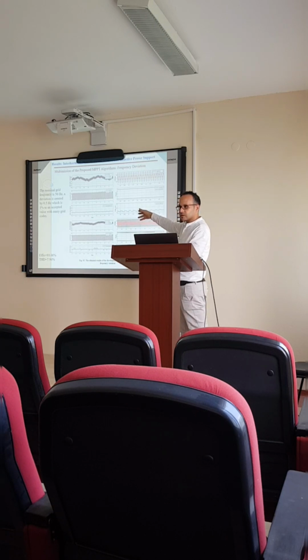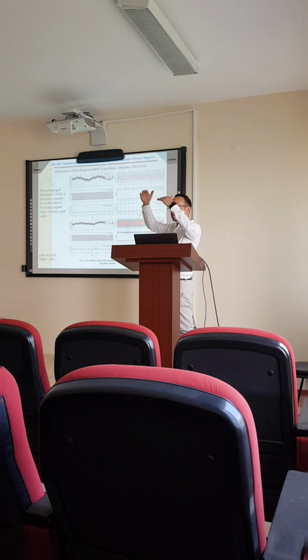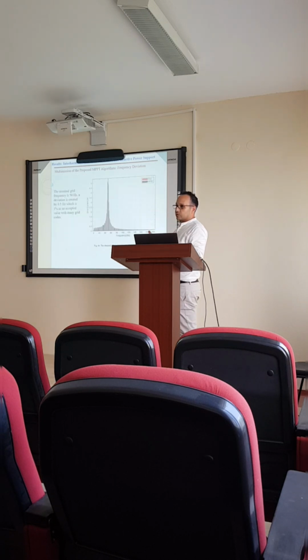So we applied this. At the moment I was watching, let's say, the grid voltage, when I changed the frequency, the grid voltage started changing a lot. It was fluctuating at that point. And maybe this is the main reason why the inverter is trying to, because of the fluctuation, not a big fluctuation, but it was fluctuating at the point of coupling. And the idea is that under this case, I think the algorithm didn't do anything.